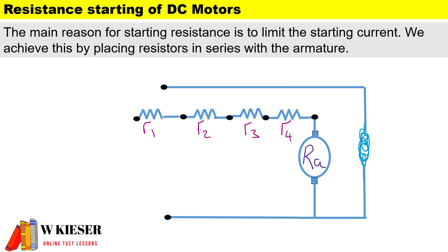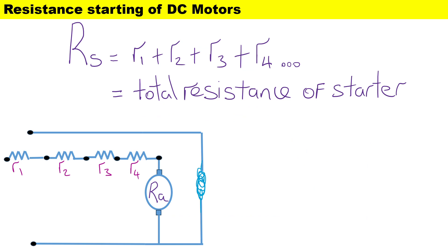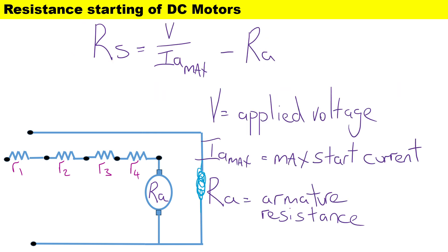In this illustration we have four elements, represented by the letter m. The number of studs will be the number of elements plus one, so in this illustration we have four elements connected in series and there are five studs. The total resistance of the starter consists of four resistors connected in series to one another.